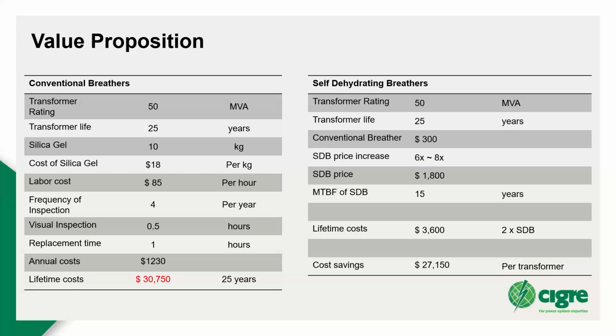Then when you shift from traditional breathers to self-dehydrating breathers, the initial purchase price may go up by 6 to 8 times. So if your original breather was around $300, now you may spend around $1,800. Over a lifetime of 25 to 30 years, you will probably need 2 such breathers because of the MTBF, so the lifetime cost is roughly $3,600.